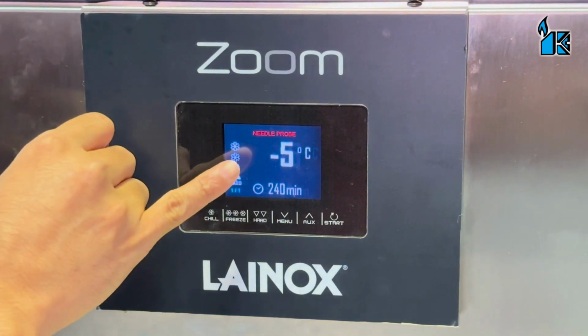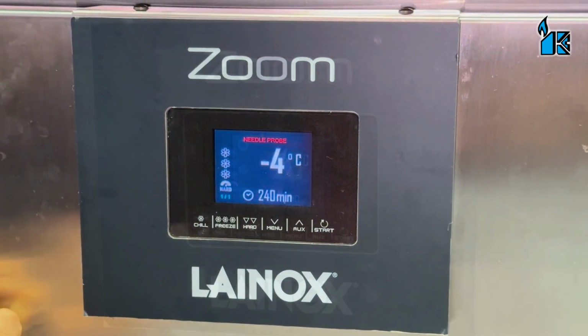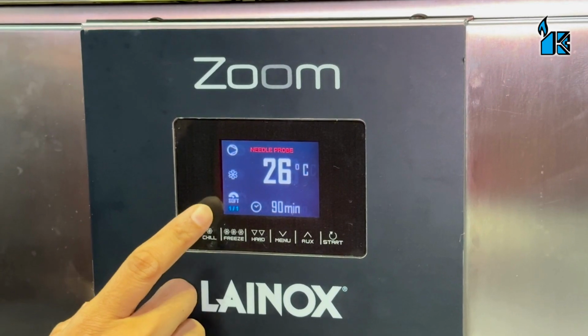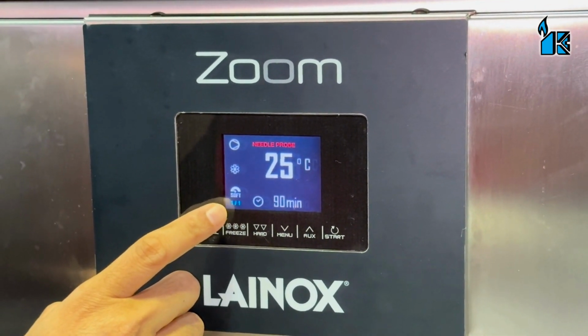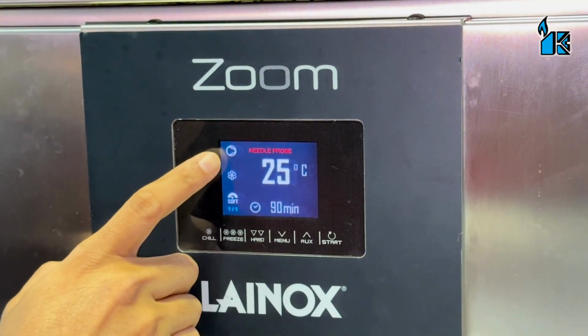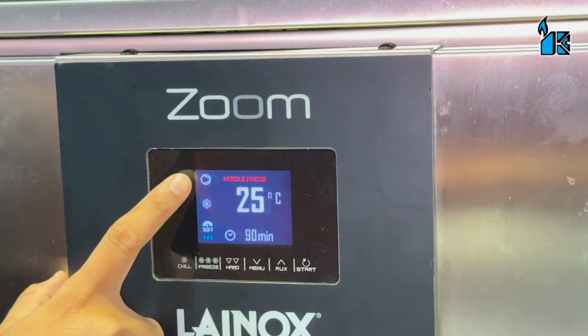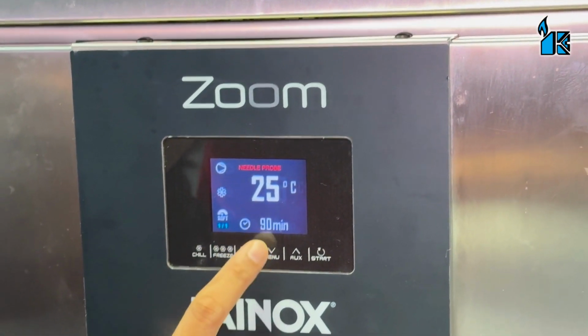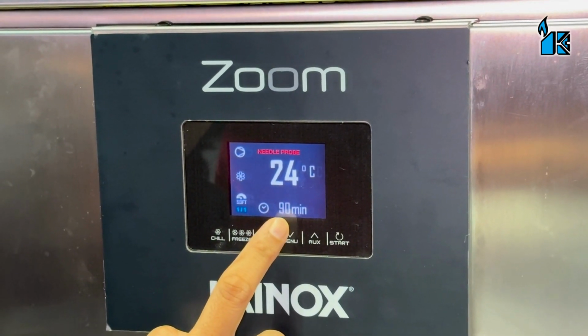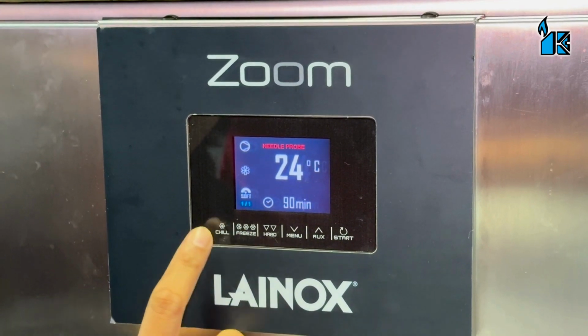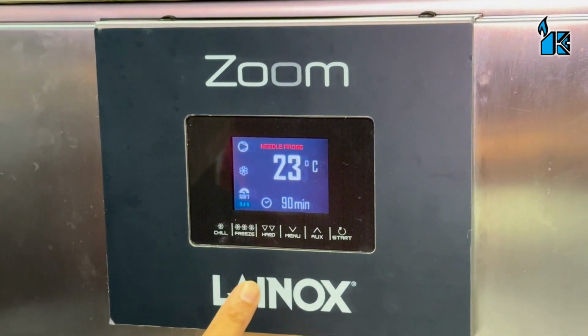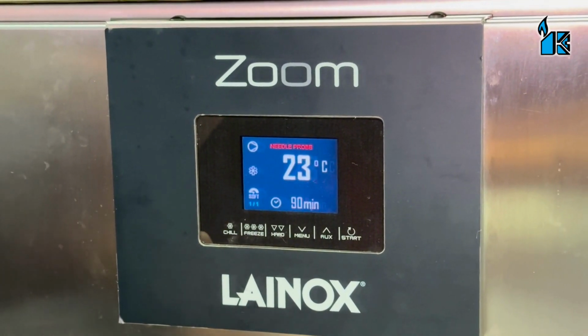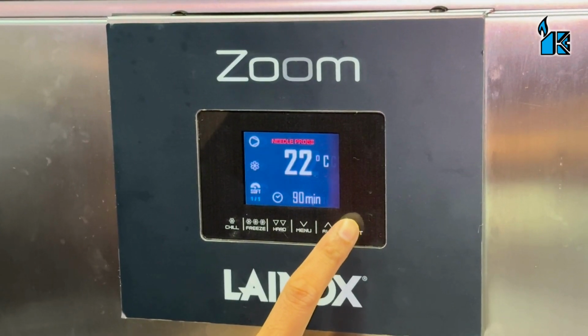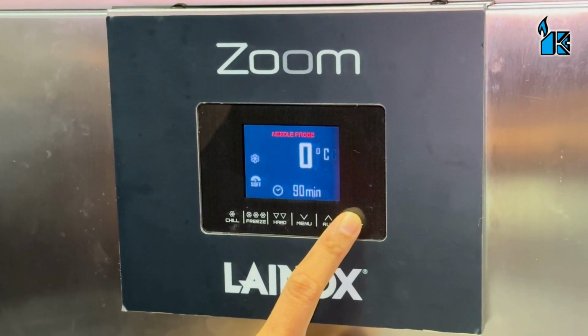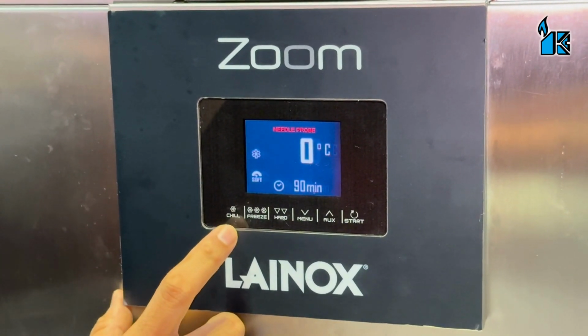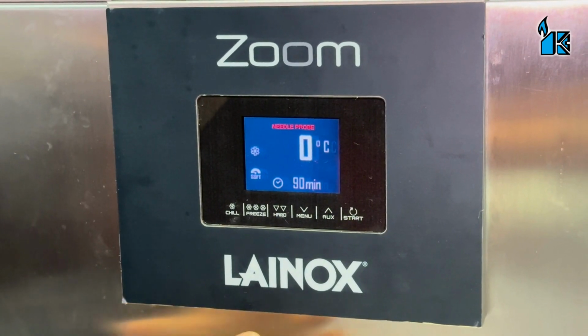Currently the chamber temperature is -5. When you press the start button, the panel will show soft mode. 1/1 means a single phase. This is the symbol that the compressor is running. This is the current temperature inside the chamber, and this is the time remaining. The time will count down until 0 minutes, and the machine will go to holding mode. If you want to stop or pause, you can press the start button once. If you want to go back, just leave it like this, and then the machine will stop immediately.